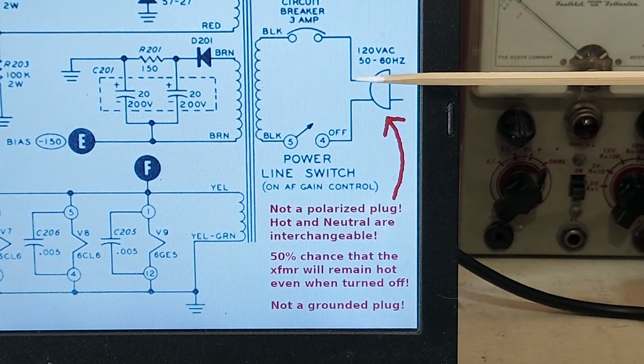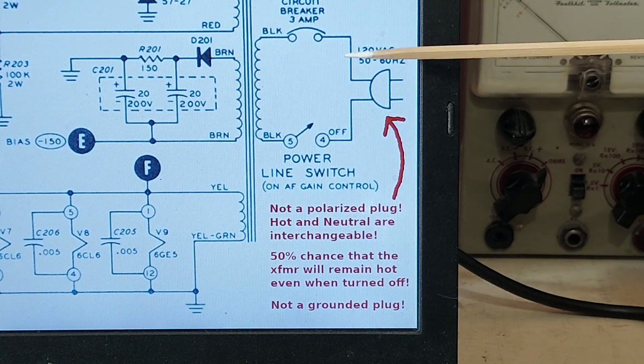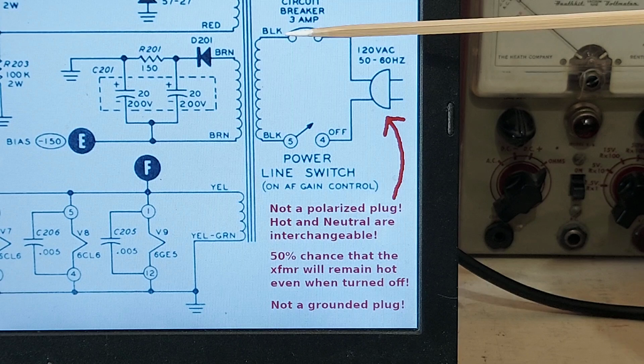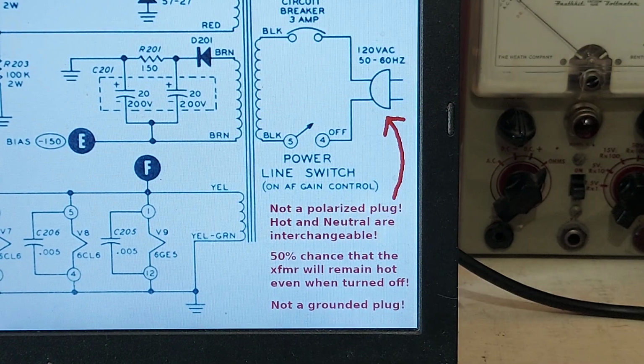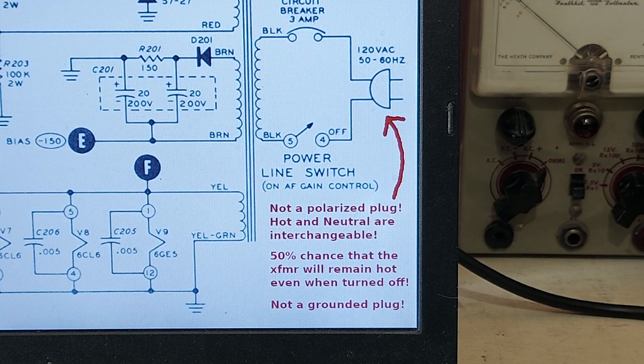If you've got it plugged in such that this line is hot, it's always connected to the circuit breaker, which is always connected to the transformer. The transformer's always hot. If anything goes wrong in that, even when it's turned off, the transformer's hot, and it happens a lot, you might be surprised. If one of those windings shorts to the core, and the core's bolted to the chassis becomes hot, you've got your hands all over that thing and you touch something that's grounded, boom, you're dead.